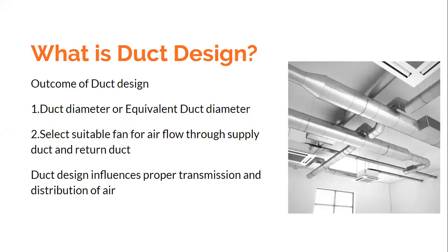So what is duct design? Duct design primarily involves calculation of duct diameter, if it is a circular duct, or if it is a rectangular or square duct, we calculate what is known as equivalent diameter. So this is one of the important outcomes of duct design. The second important outcome is you need to be in a position to select a fan of appropriate capacity. Appropriate capacity means the fan which would be able to flow the air through the supply duct and return duct with the minimum possible power consumption.